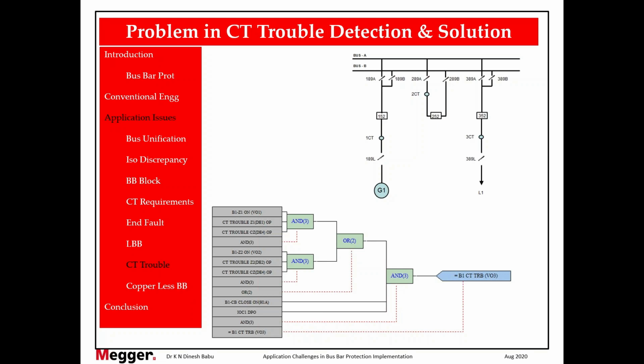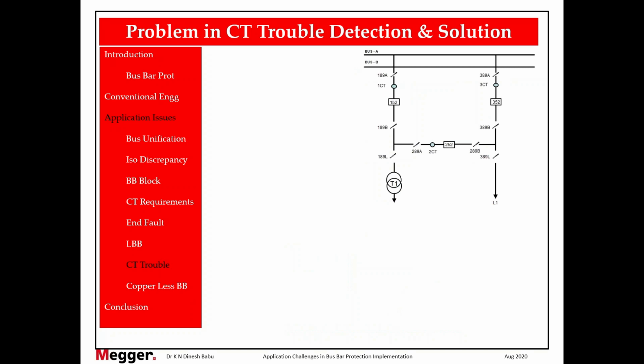whether the breaker is closed, whether undercurrent is picked up. If all are satisfied, CT trouble in that particular bay is noted. So this will be repeated for all the bays using this logic. We can identify which CT is having problem.